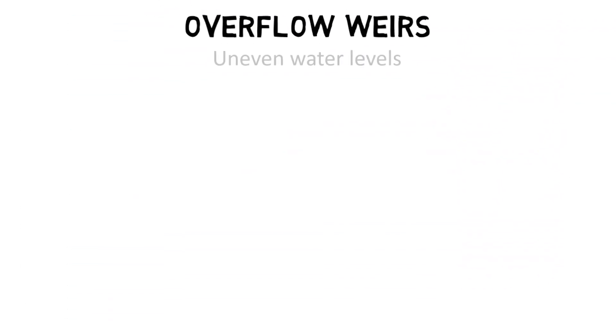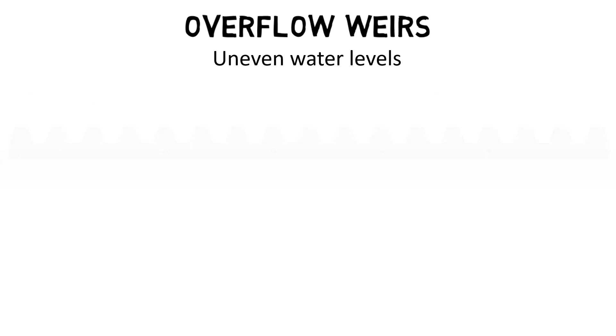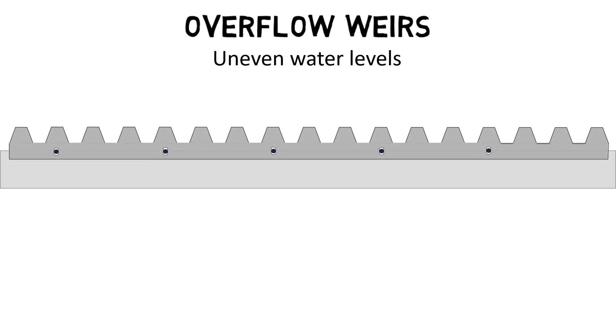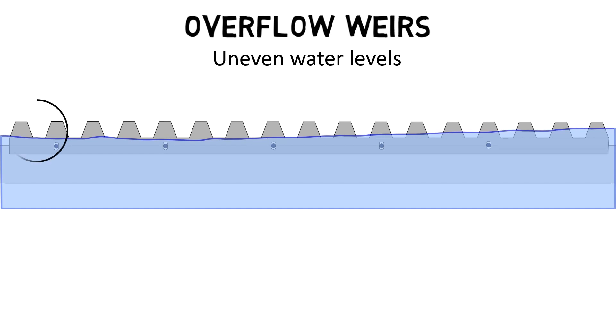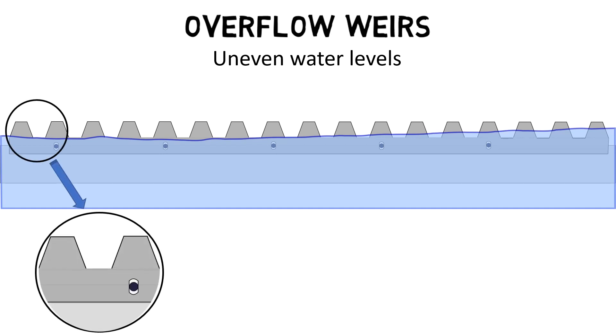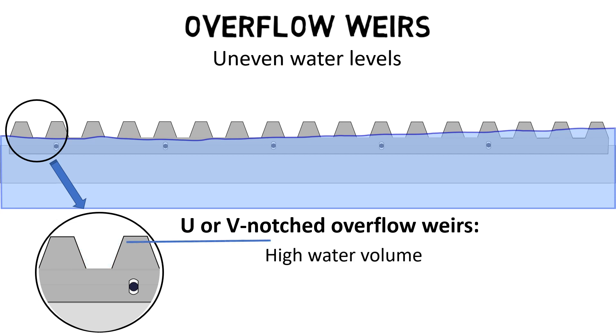The water level in clarifiers is never completely even, but at the same time the overflow of water over the effluent launder edges must be uniform. To balance out the differences in the water level, effluent launders are usually equipped with a V or U notched overflow weir. The V or U notched weir regulates the overflow water amount and therefore accounts for uneven water levels in the clarifier basin.